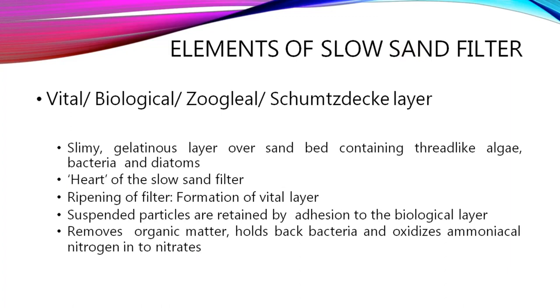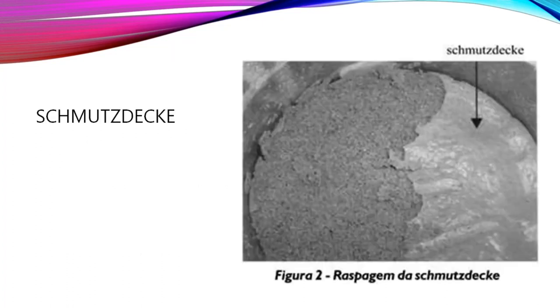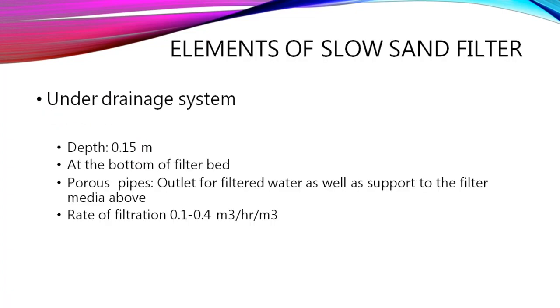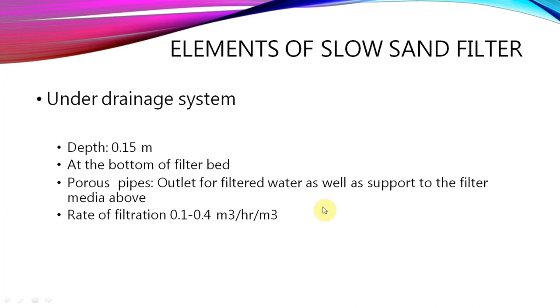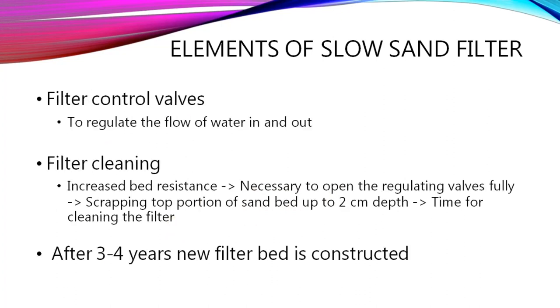Filtration and storage are the most vital parts in slow sand filters, whereas storage is not very important in rapid sand filters. The under-drainage system is 0.15 meters at the bottom of the filter bed - porous pipes drain water to the central supply. The rate of filtration is 0.1 to 0.4. Valves regulate the flow of water and control the outlet after purification.